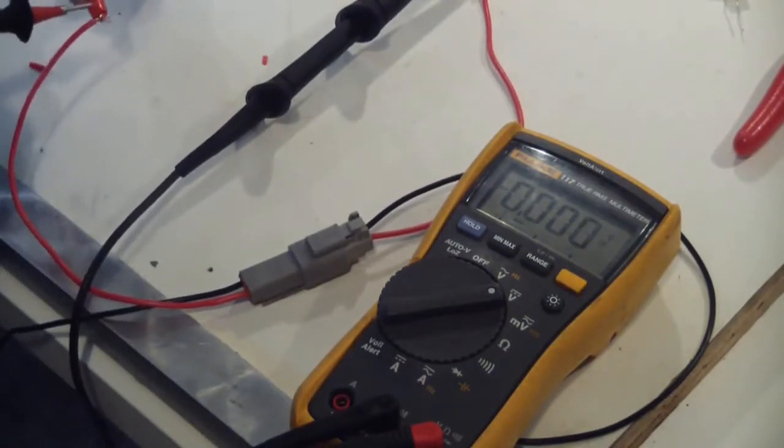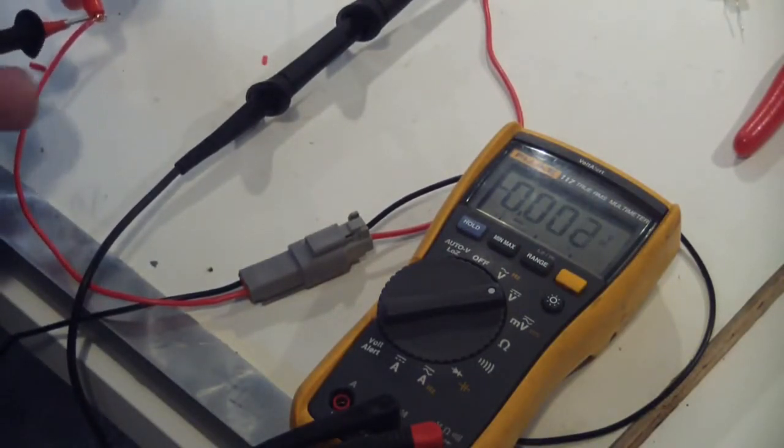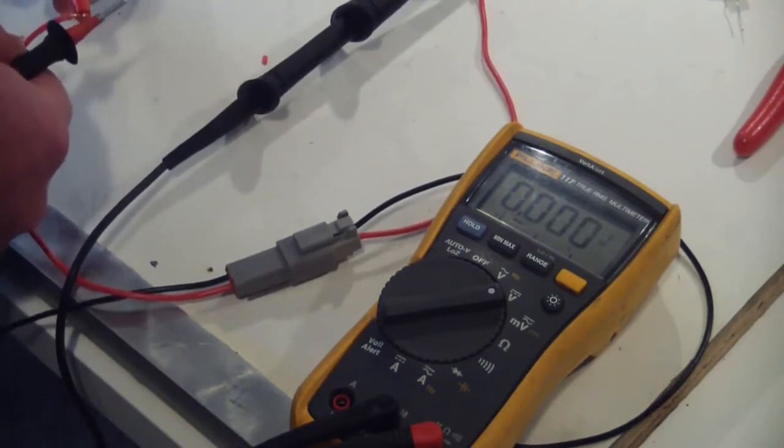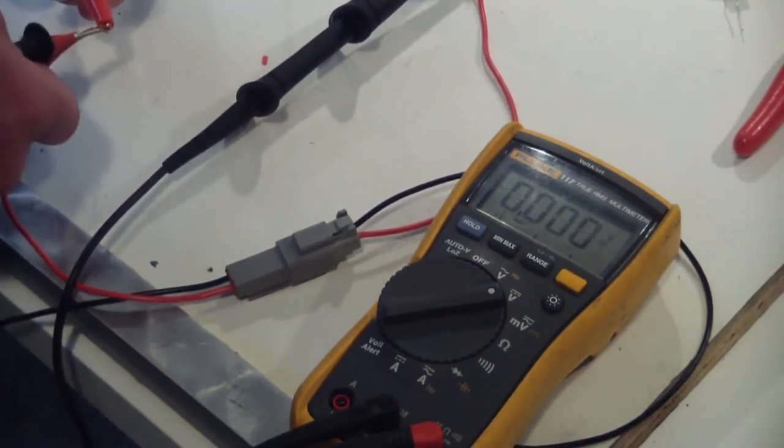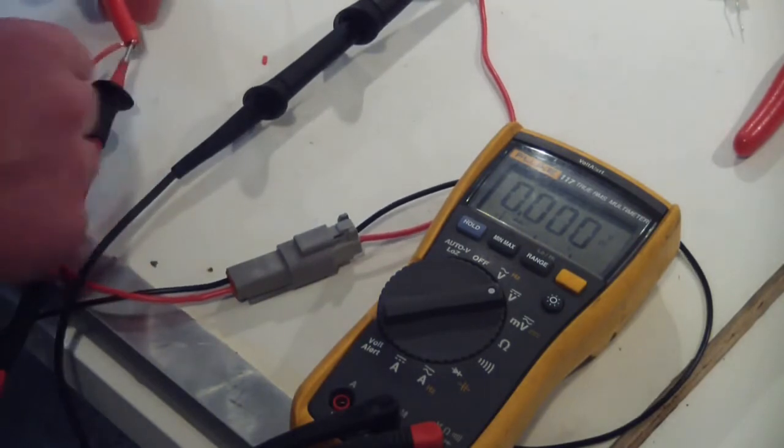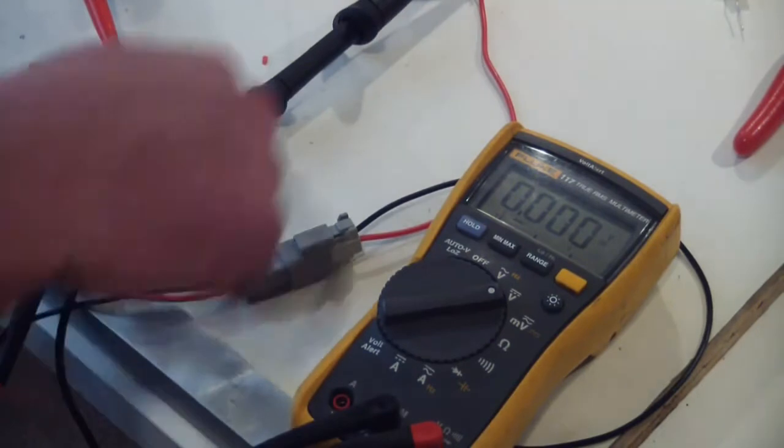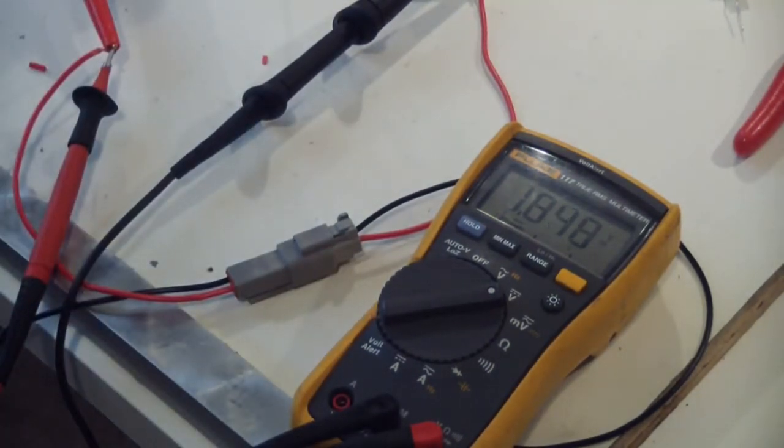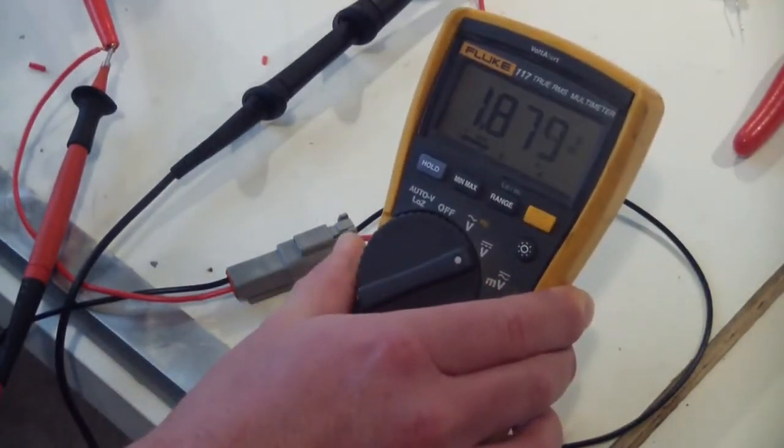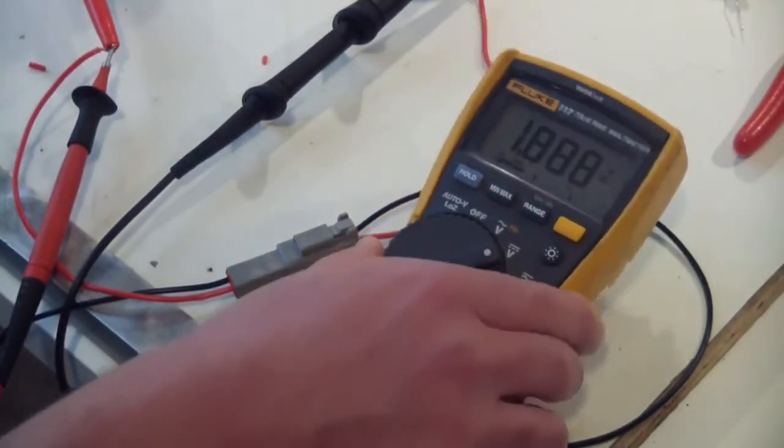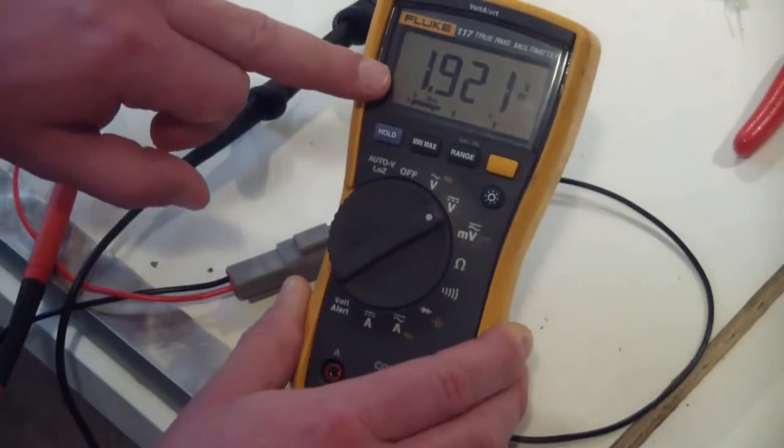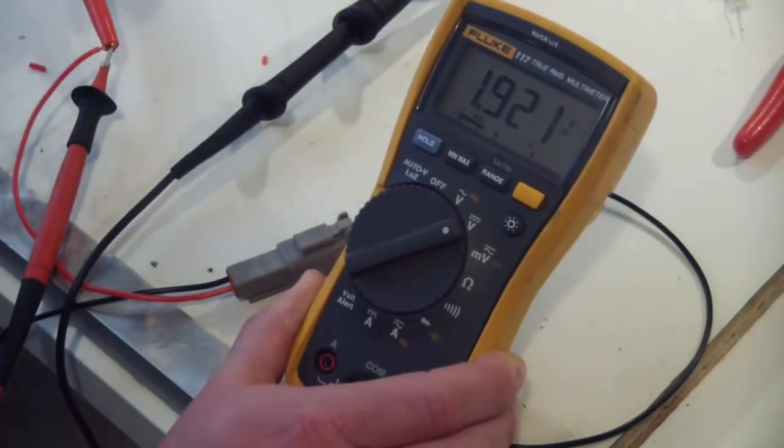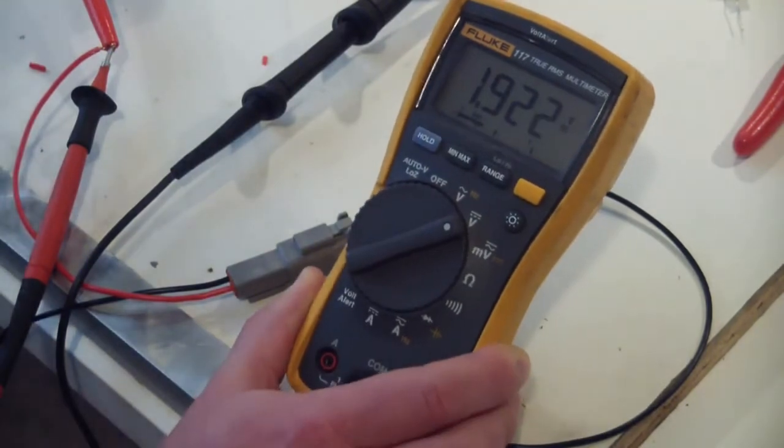What you're going to do is you're going to hook up your leads to the section of wire that you think is bad. You're going to have it de-energized while you do this. And then what you're going to do is you're going to energize it and you're going to see the voltage drop through that wire. So we can see here, we got a 1.8 volts DC drop. We can see we almost got a two volt drop there. So we know that between this lead and this lead, there is a problem.